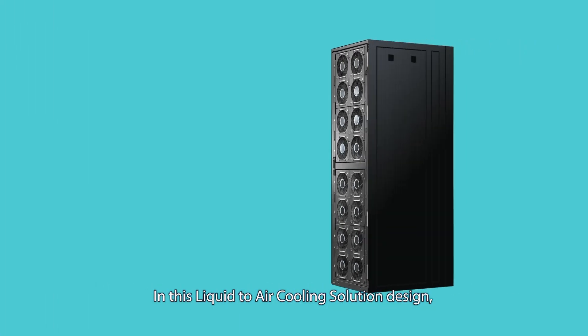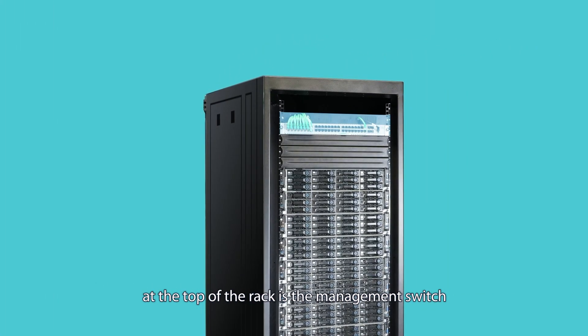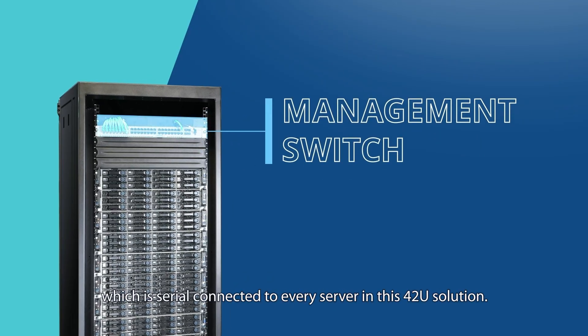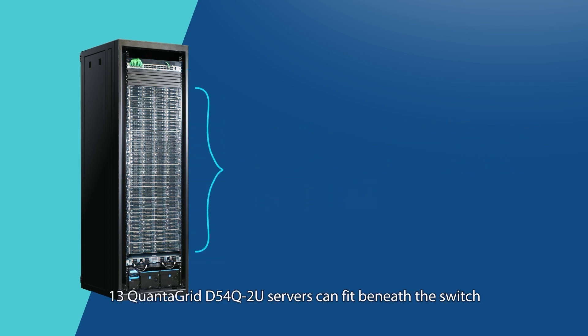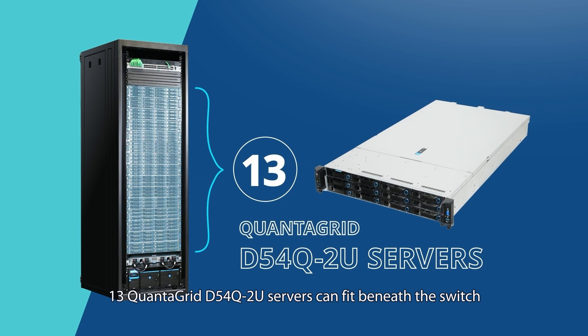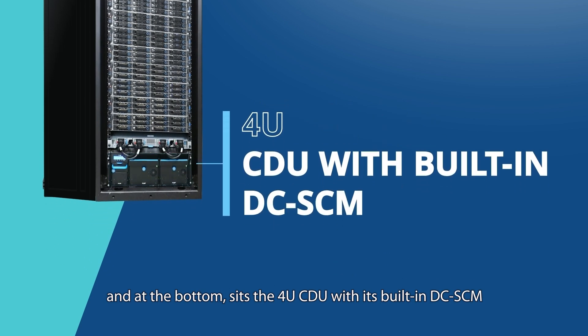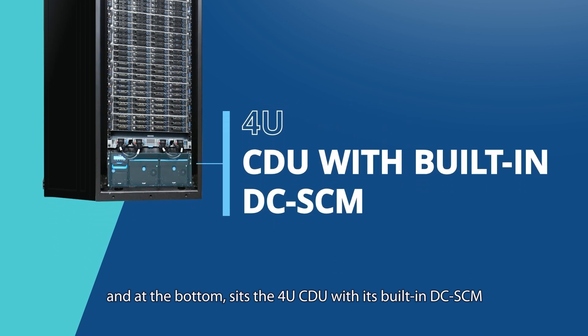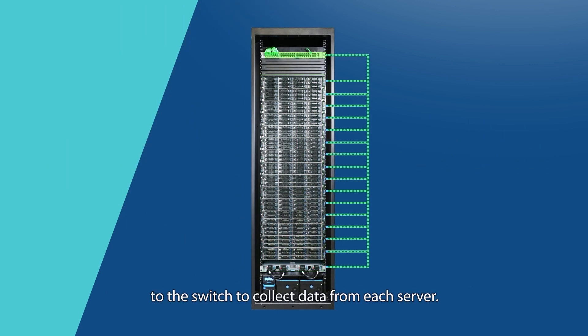In this liquid-to-air cooling solution, at the top of the rack is the management switch, which is serially connected to every server. In this 42U solution, 13 QuantaGrid D54Q-2U servers can fit beneath the switch, followed by a 1U redundant power sled. At the bottom sits the 4U CDU with its built-in DCSCM for smart rack management, which connects to the switch to collect data from each server.